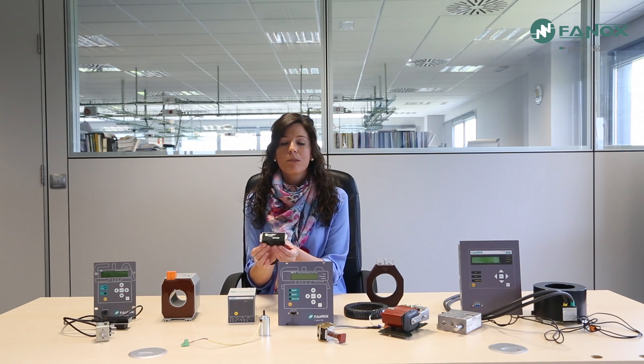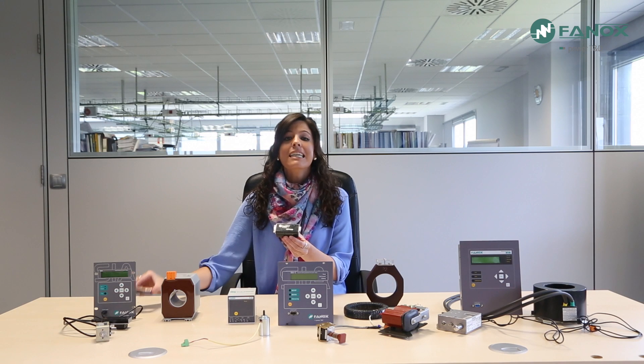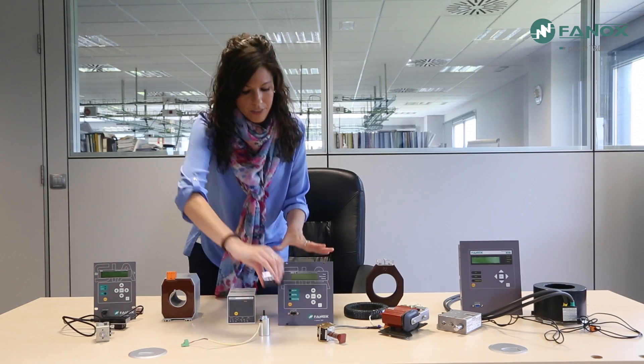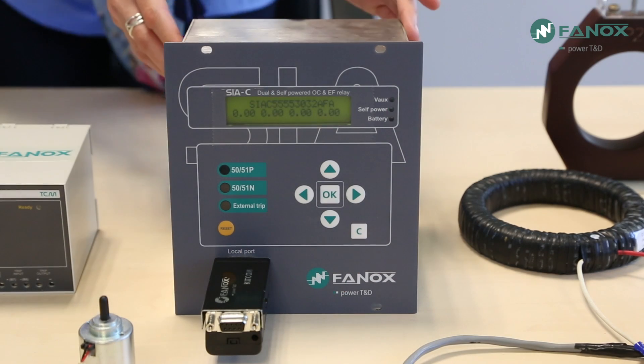How can correct installation of the self-powered relay be verified? Due to the lack of auxiliary power, it might seem the only way to verify installation is after the relay is powered up — however, this could be dangerous, because if a fault occurs and something is incorrect in the relay, the transformation center would be unprotected. To solve this, Fanox offers the Kitcom — an external battery device powered by two AA batteries, connected to the front port of the relay. Since relays can have a DB9 port or USB port, there is a Kitcom for each situation. Once the Kitcom is connected and its switch is pressed, the relay is powered on. Combined with a test menu, this allows checking not only the relay hardware but also the outputs and trip circuit, verifying everything is correct before the transformation center is powered up.